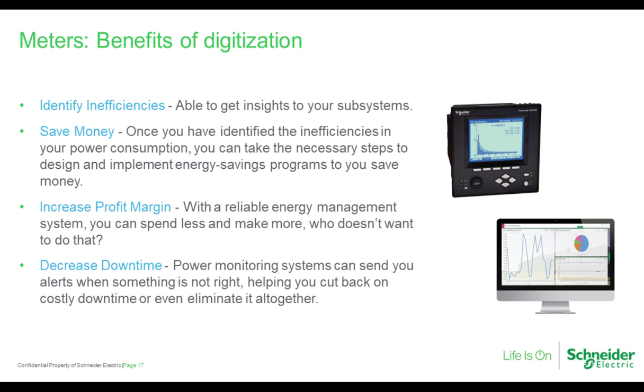Decrease downtime. Our monitoring systems can send you alerts when something is not right, helping you cut back on your costly downtime or even eliminate it altogether. These are just some of the benefits. We can also look at what's happening outside of the system, what kind of energy you're getting in from your utility source, and where we're at with that. And seeing, sometimes it's the utility that's causing problems within the systems. We can identify those problems and report back to the utility.